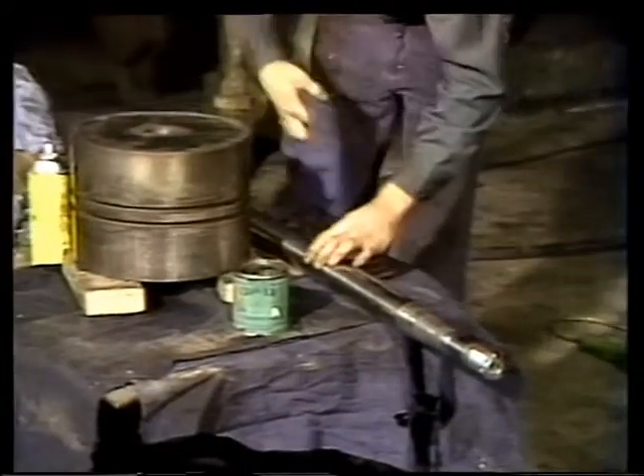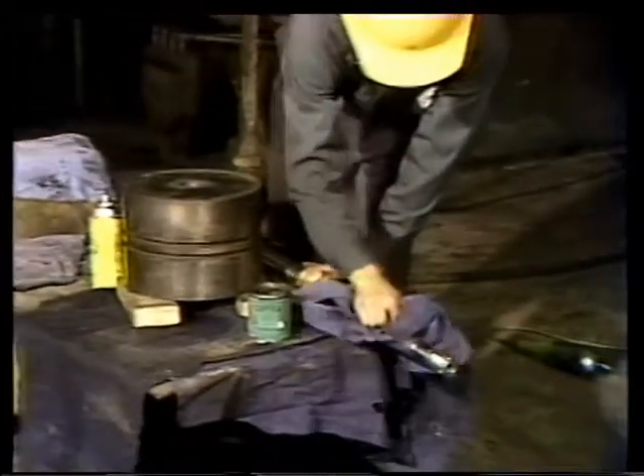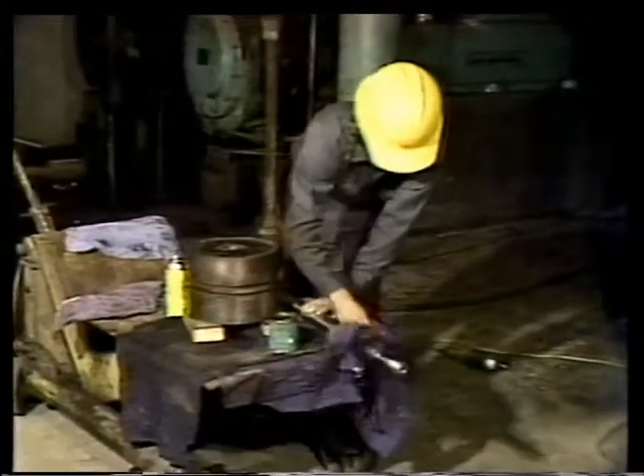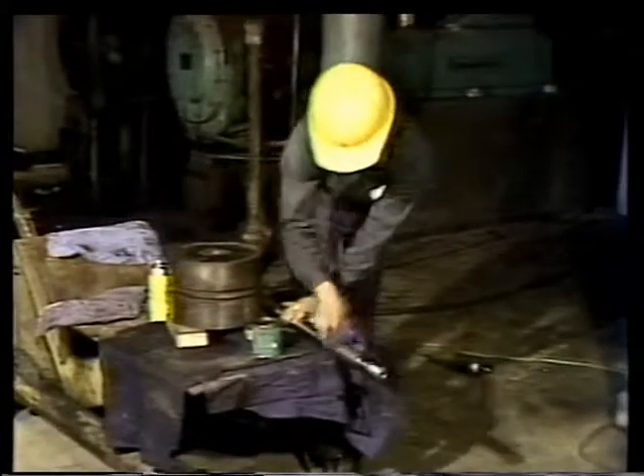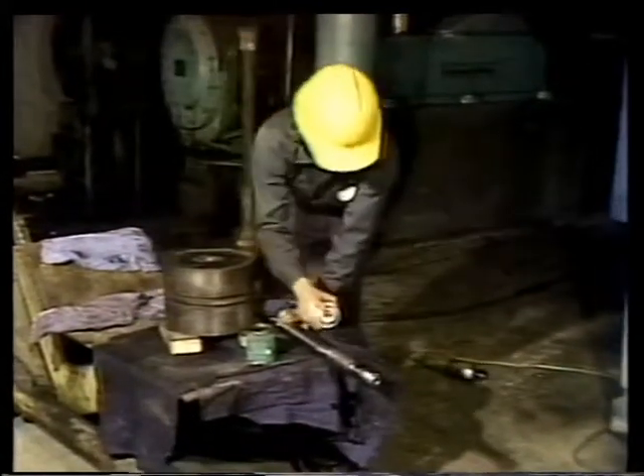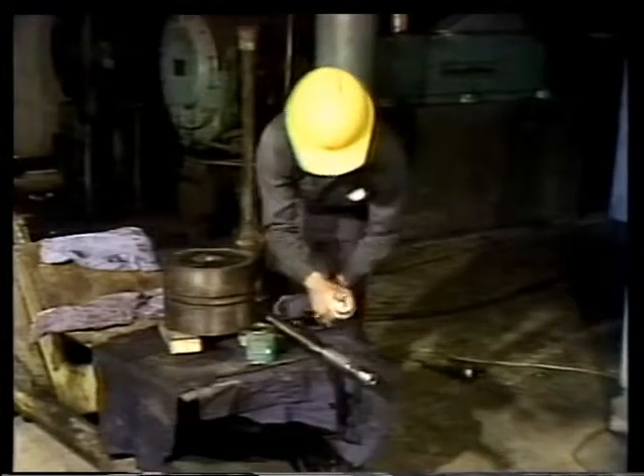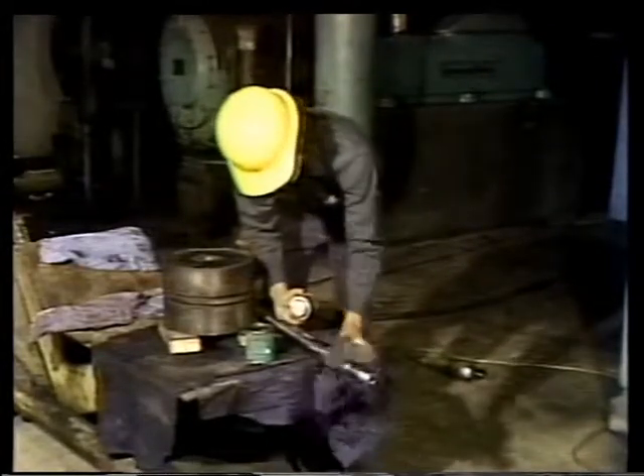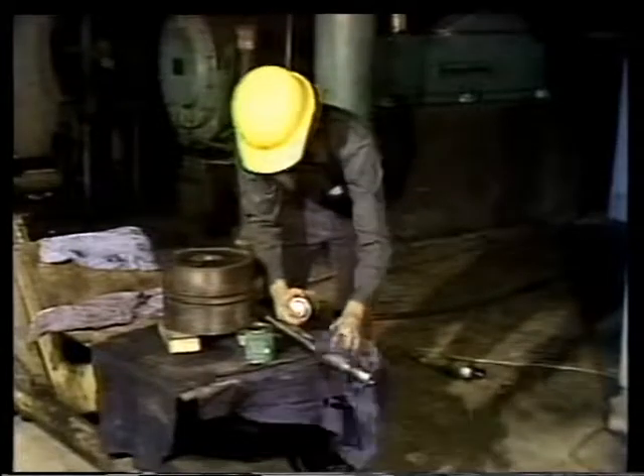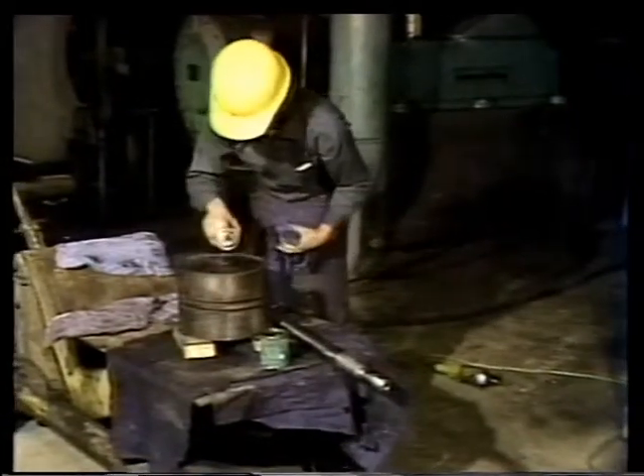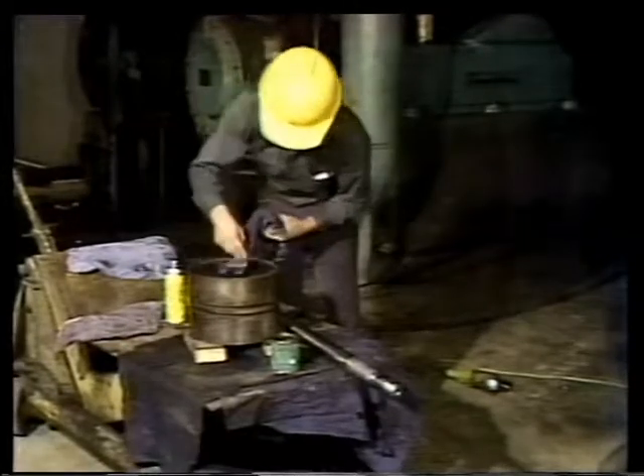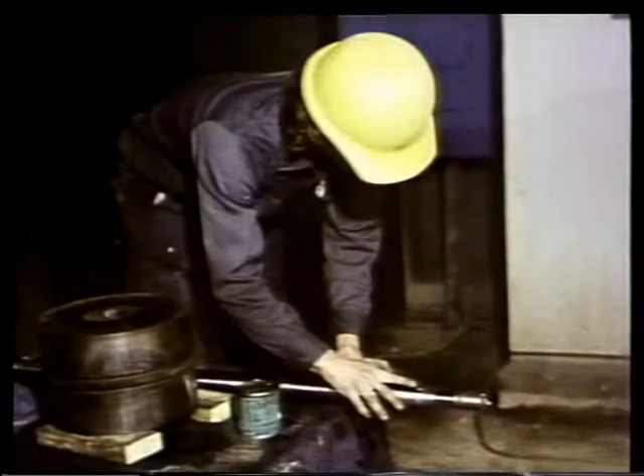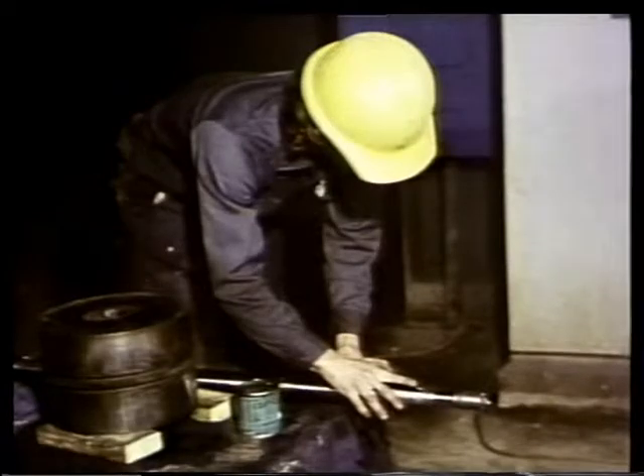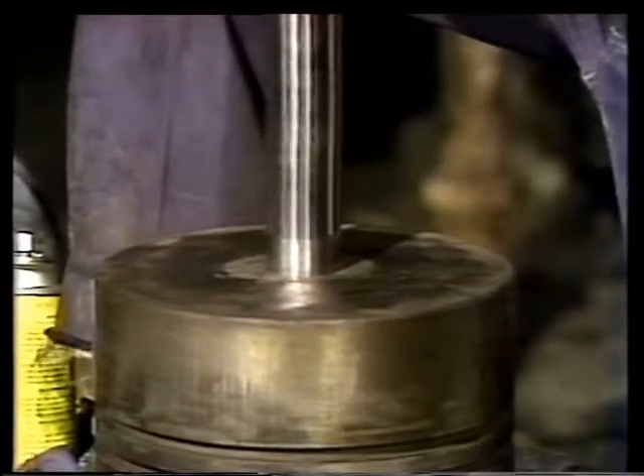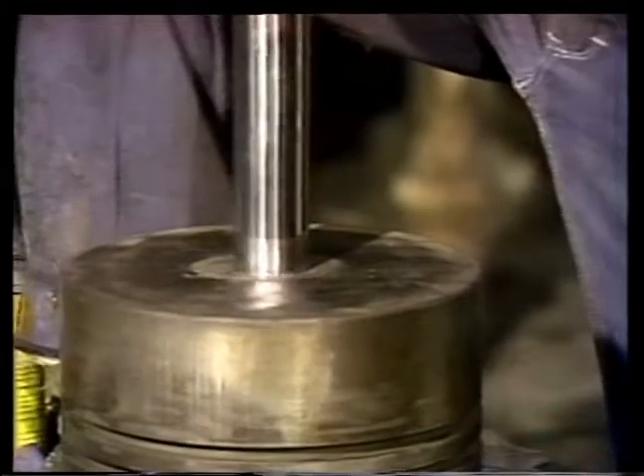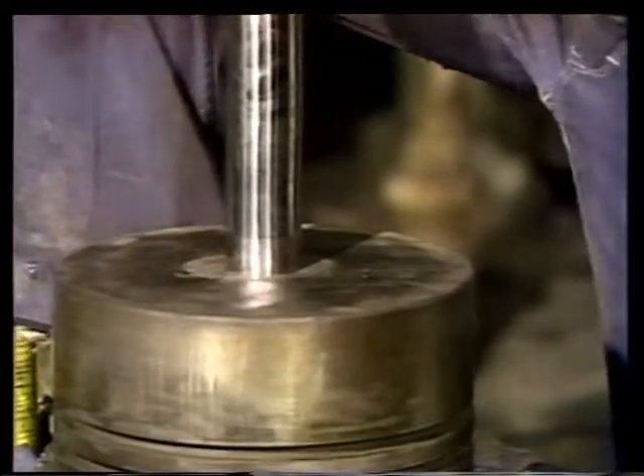Clean the worn down lapping compound off the rod and piston and wipe away all remaining residue with a clean cloth and solvent. Then apply more lapping compound and continue grinding in until you feel that the piston and piston rod are making good contact. There'll be some resistance between the piston and the rod.